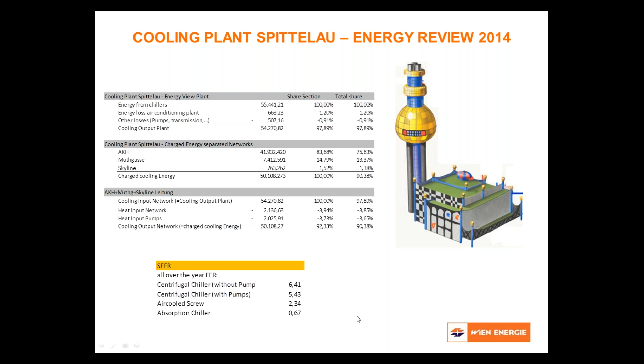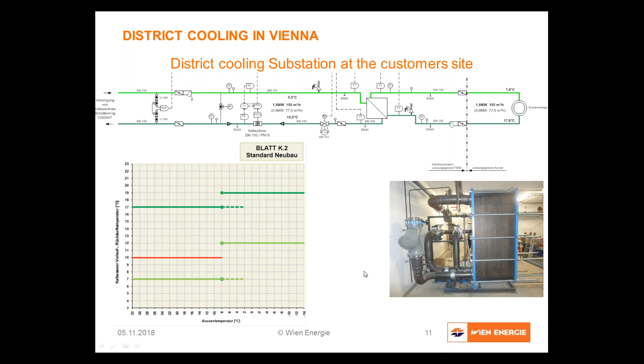So we support customers - here is the outside temperature, here is the cooling temperature. For high outside temperatures we support the customers with 7 degrees. In wintertime, for low outside temperatures, we support them with higher cooling temperatures, because we want to use free cooling - in wintertime, if the Danube Channel water or the river water is very cold, we can support the customers with free cooling, and that makes the system even more efficient.